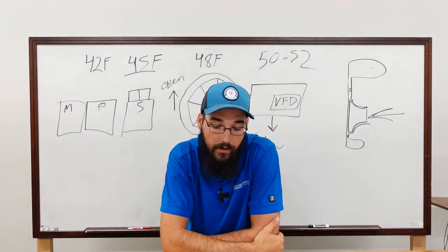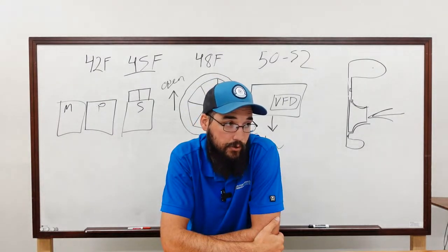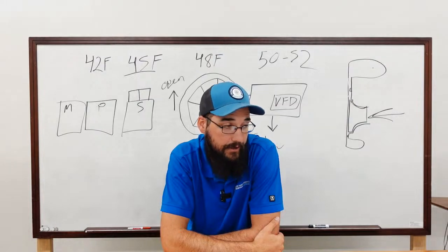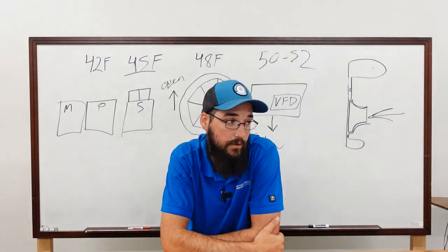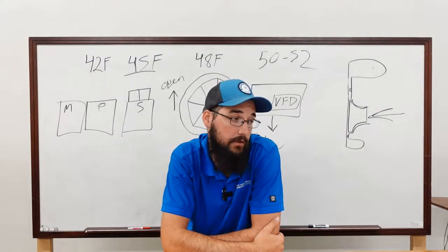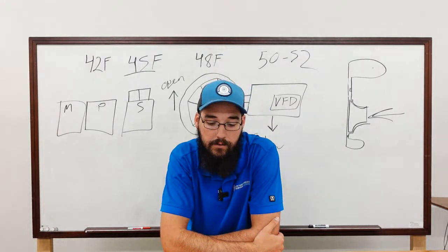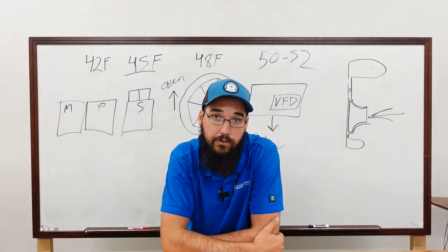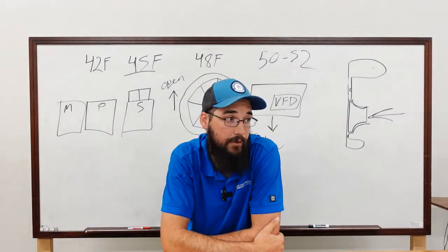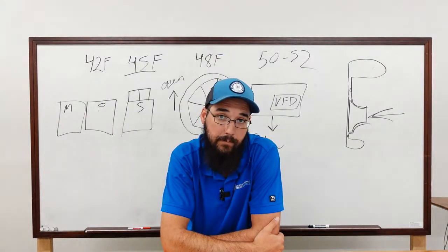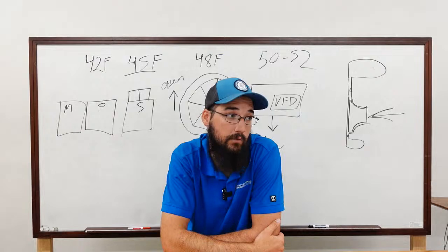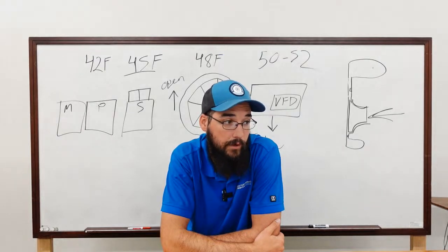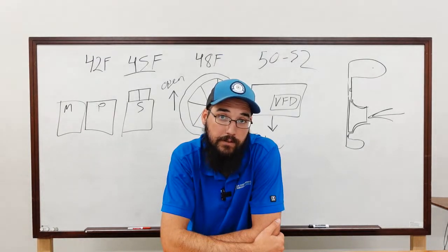Anyway, once you've got that under control and the chillers are no longer surging, you should then make a trip to the cooling tower and see why in the world is my water so hot? Because that's what controls that. That's when you get to diagnose the fan issue and realize that you've only got half of your condenser water cooling capacity. So we needed two towers, we only have one tower, but we also still need to provide cooling to this building.